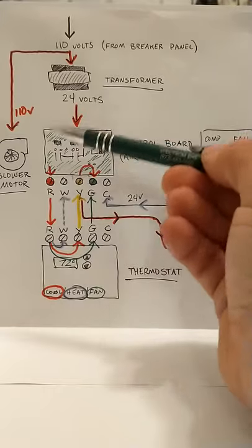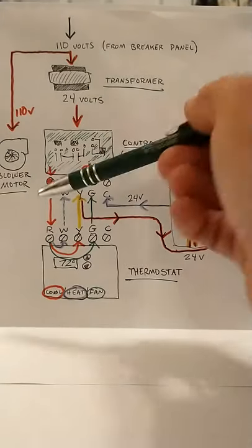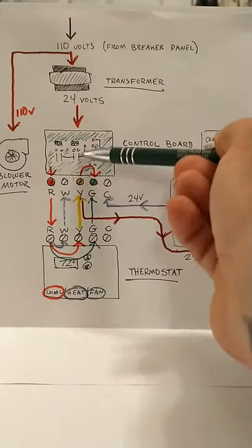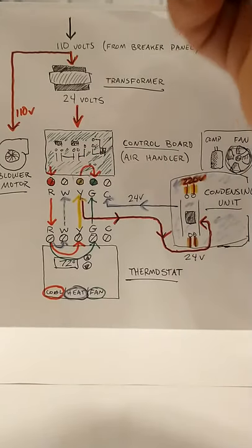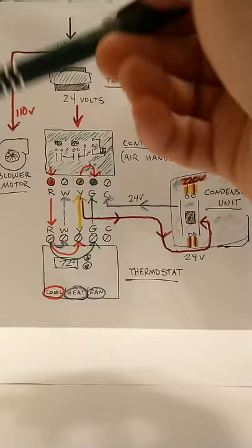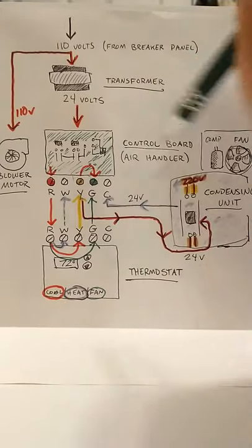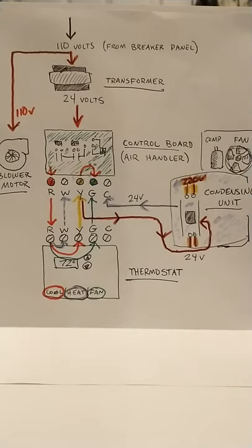And the furnace or boiler or whatever it may be will kick in. So, for example, your inducer motor, if this is a furnace, your inducer motor will start. The gas will fire up. The blower will kick in. Your heating system will come on. And everything else is out of the circuit. Your condensing unit won't start. And it's just straight heating.